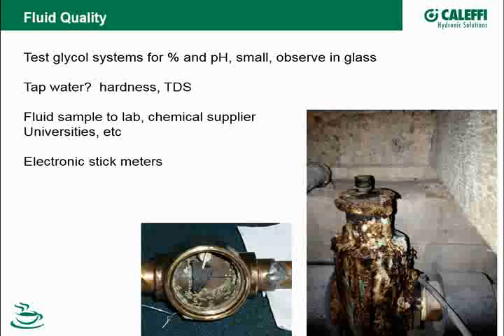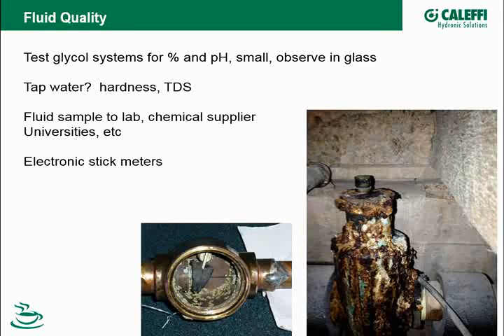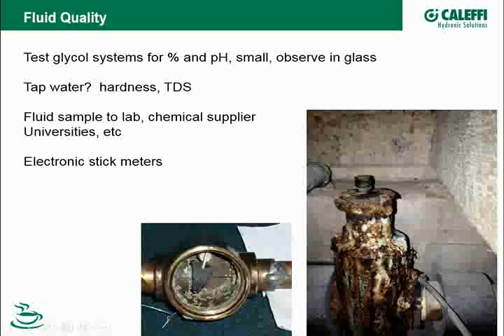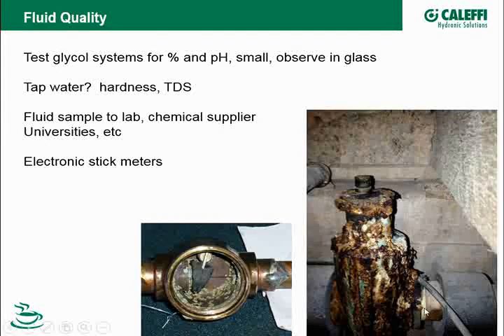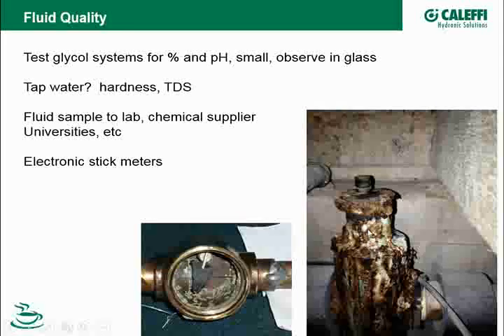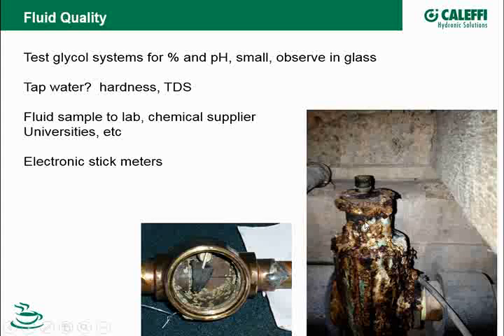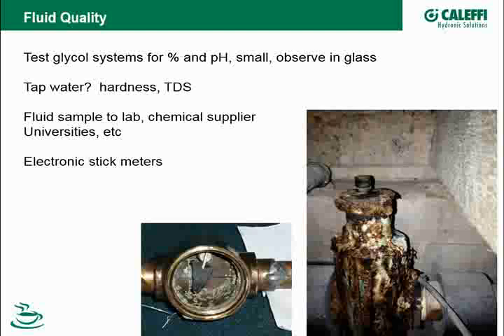If it keeps dropping, there's a good chance you've got oxygen getting into that system, or the glycol's been overheated and stressed. And you'll see that more in solar systems, where you can go into stagnation conditions and the glycol gets overheated, the inhibitors break down, and then the pH drops. And, of course, once the pH drops, you can get a condition like this little vent over to the side here, where it gets pretty aggressive to different things. You can see that, obviously, that vent's leaking out of the cap. Something got stuck under there, and now the fluid's coming out. But you can see it's kind of attacking that brass in there. So there's probably something pretty aggressive in that fluid, and I would bet that's a glycol that's been compromised, and the pH is dropping, and it's attacking some of the brass and copper components in there.